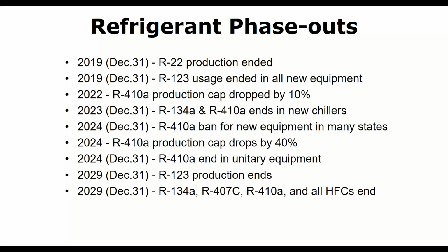Obviously, R22 production has ended, and R123 production for new equipment has ended. There's a difference there: one means they can't produce the refrigerant anymore, the other means they cannot produce equipment that uses that refrigerant anymore. Both happened a couple of years ago. Obviously, you can still get R22 refrigerant at supply houses, it's just that no one can manufacture any new refrigerant. So it either has to have been stockpiled, or it can be reclaimed and professionally cleaned up, then redistributed somewhere if need be.